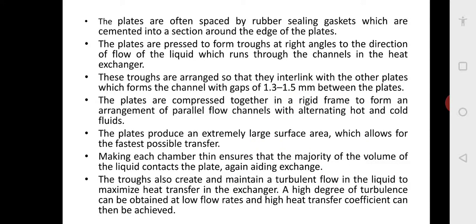The plates are often spaced by rubber sealing gaskets. To seal between the alternate plates, sealing gaskets are used. The plates are pressed to form troughs at right angles to the direction of liquid flow, which runs through the channels in the heat exchanger. These troughs interlink between the plates, forming channels with gaps of 1.3 to 1.5 mm. The plates are compressed together in a rigid frame to form parallel flow channels with alternating hot and cold fluids, producing an extremely large surface area for the fastest possible heat transfer.